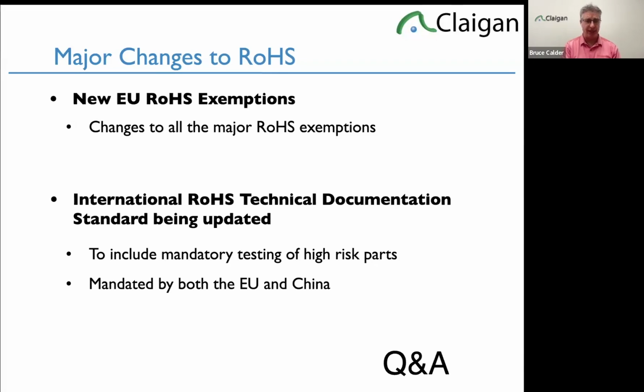IEC 63000 would have to be declared - that's when you have to update the standard in your declaration of conformity. So your single pager should say compliant to RoHS directive, and below it should say using technical standard IEC 63000 2016 or 2018, whichever it is. When it gets updated to the 2026 version, that's when you'll need to update your declaration of conformity to that version.